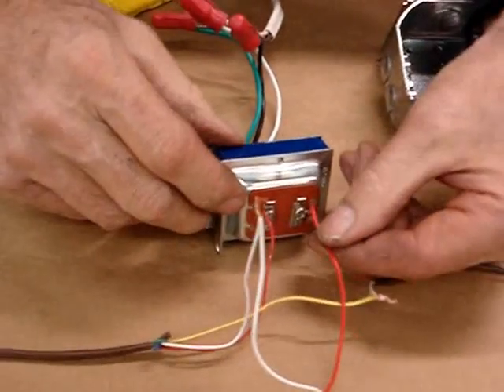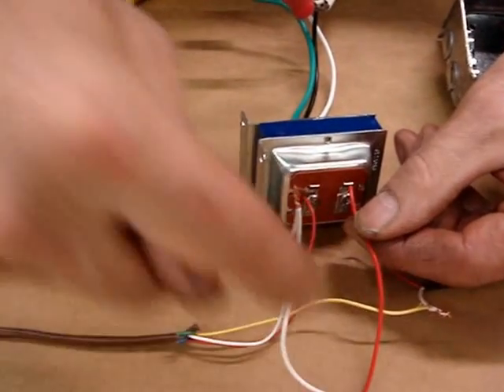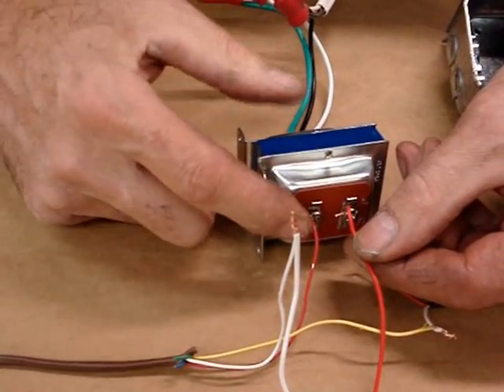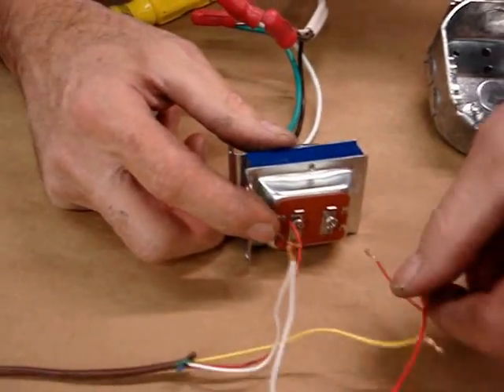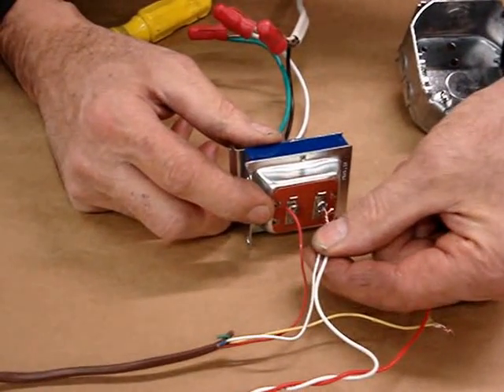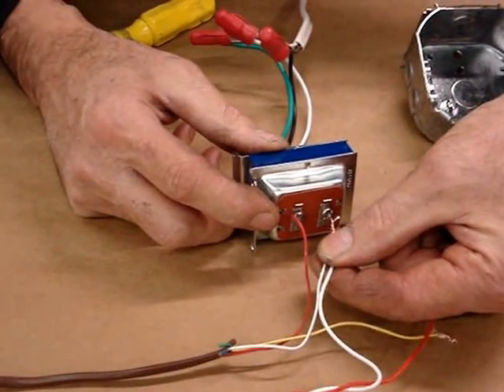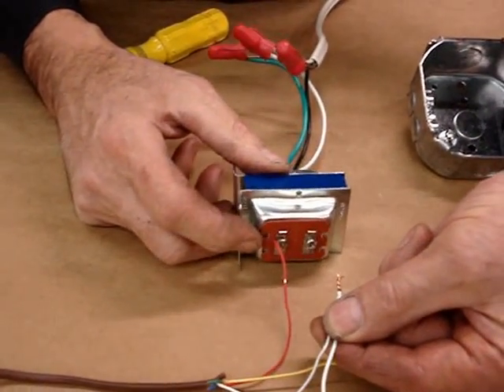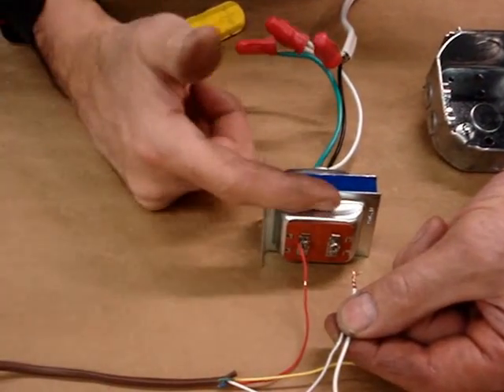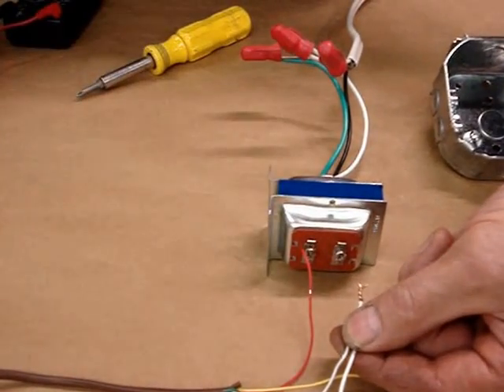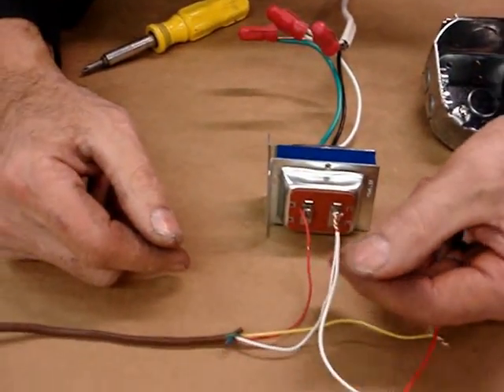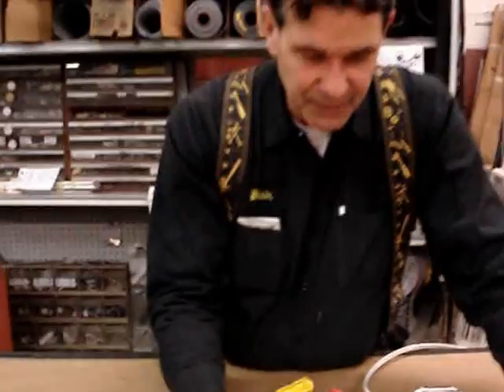So instead of the electricity leaving, going to my doorbell button, and coming back, the red wire already goes to the doorbell. I can just take this particular wire and touch it to the transformer, so I can ring it from the basement. That gives me a chance to check whether the transformer is good or the doorbell is good, before worrying about what may have happened to the wires in their travels back and forth.